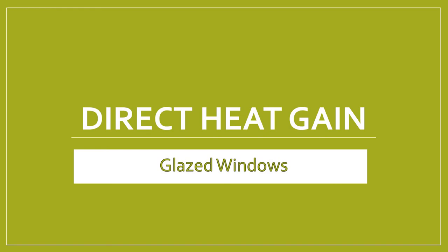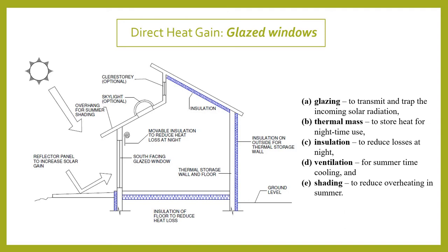Direct heat gain is achieved through glazed windows. The glazing transmits and lets heat come inside. You then put in a large thermal mass — thermal storage in the wall and floor — so that heat is stored within the building. You also provide insulation on your wall, ground, and roof so that there is no heat loss during the night.